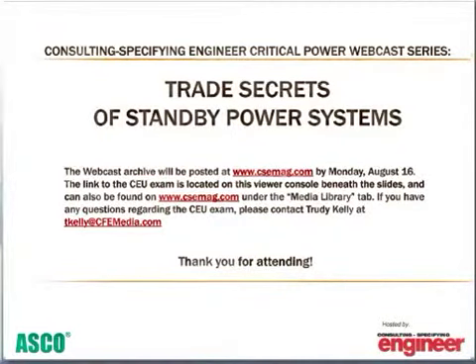If I could throw in something here, I've had some experience specifically on this question, and the rule of thumb that I've used in the past was somewhere between 4 and 5 times. So if you've got 0.07 gallons per kW per hour, you'll multiply that by, say, 5. And if you have a little bit of excess fuel, it really doesn't make any difference.